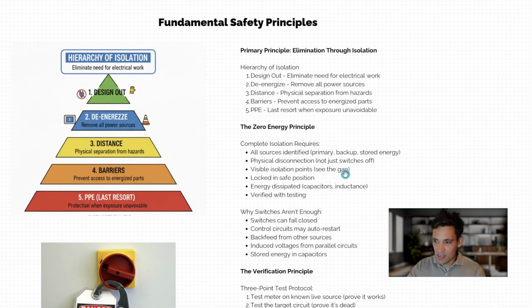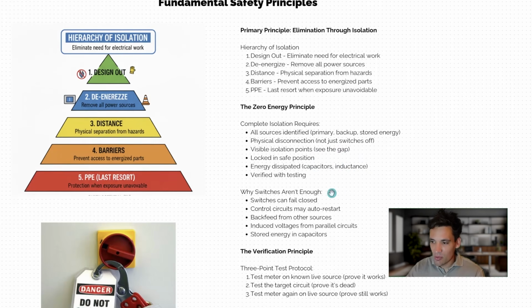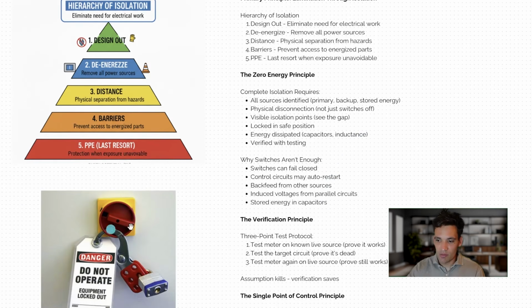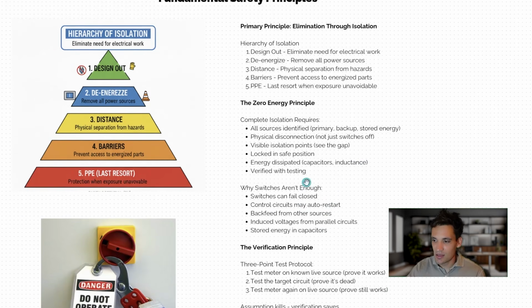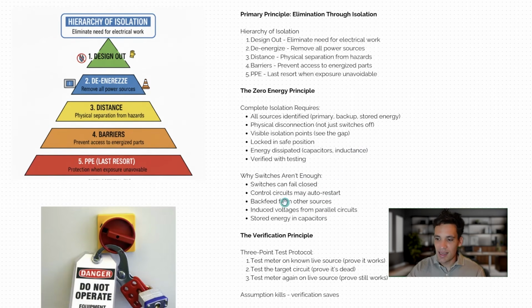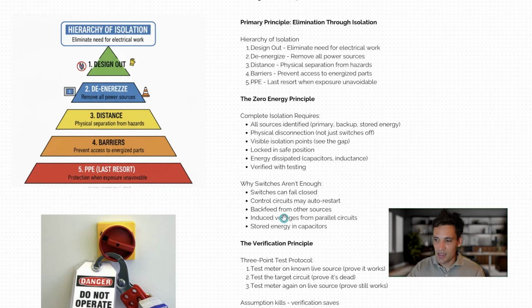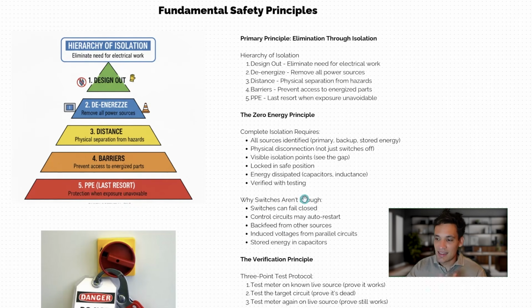You want physical disconnection, not just the switch being off, but a physical gap between the energy source, the voltage source, and where people are working. Visible isolation points, and we'll talk about this more when we talk about the lockout tagout procedure that people use on construction projects. Everything is locked in an off position. People working on it put a personal padlock on the work, and they have the key to it. They're the only ones that can remove it. And any stored energy in a system is dissipated.